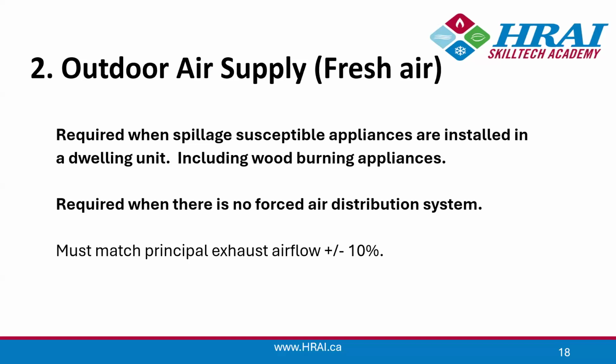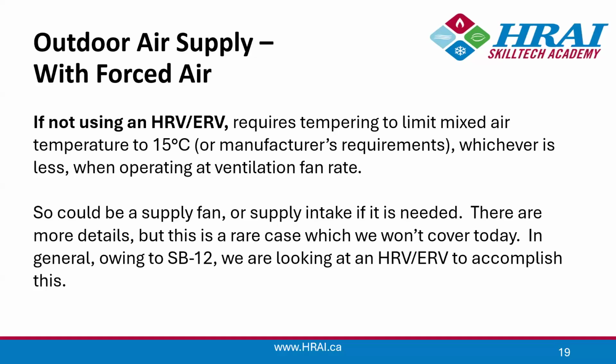And of course we also need it when there is no forced air for the distribution of the fresh air. And then of course it makes sense that we should try to match our supply air with our principal exhaust airflow, and in fact it must match within 10%. If you're not using an HRV or ERV, then this supply air will need tempering to limit the mixed air temperature to 15 Celsius. So if you're providing it to, say, for example, a forced air system, you'll need to calculate a mixed air temperature and keep it under 15, whenever you're operating at the ventilation fan rate.